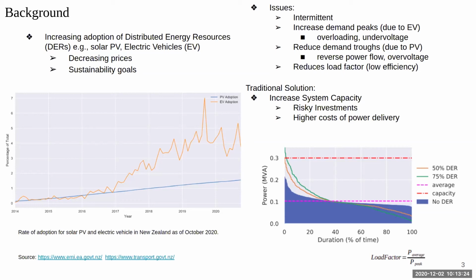These peak demands cause overloading and under-voltage. Meanwhile, during the day in residential networks where there's already minimum demand for electricity, this is further reduced by increasing adoption of solar PV on rooftops. So this trend will cause reverse power flow and overvoltage.